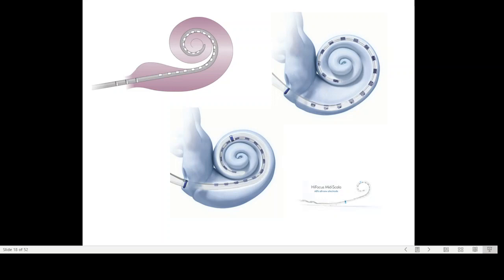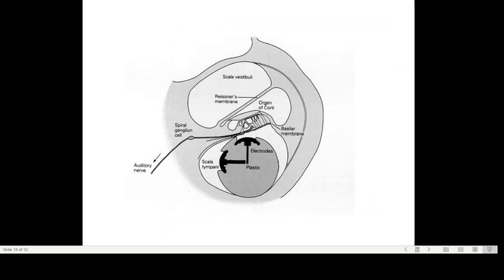There are some modifications of the cochlear electrodes as used. Either we want to make it closer to the modiolus, with hugging electrodes, with advantages and disadvantages, or laterally placed electrodes, or mid-scalar ones, which have specific indications to avoid extracochlear stimulation and are specifically advisable in cases of advanced cochlear otosclerosis.